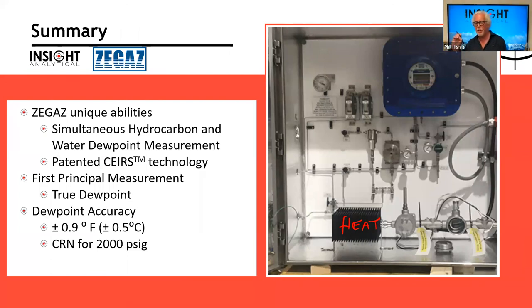So the ZEGAZ unique abilities are that they can do this simultaneous hydrocarbon water dew point with a patented technology that is very low maintenance. First principle measurement, it is truly measuring dew point, not calculating a dew point, and gives us a dew point accuracy of about half a degree C.